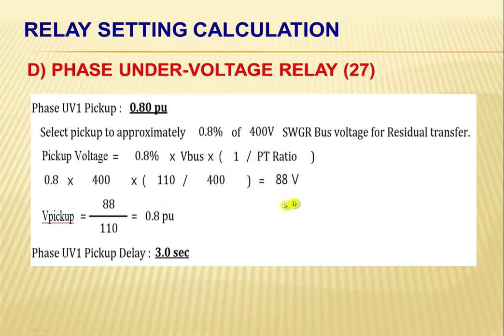So we have here the value of 88 volt over the 110 volt. This is for the secondary. That's why our phase under voltage pickup is 0.8 per unit also. For our phase under voltage pickup delay, it should be a little bit longer. It's okay because we have here 3 seconds. Beyond that, it's not acceptable anymore because a prolonged under voltage on our interconnected devices will create overheating on our interconnected components.